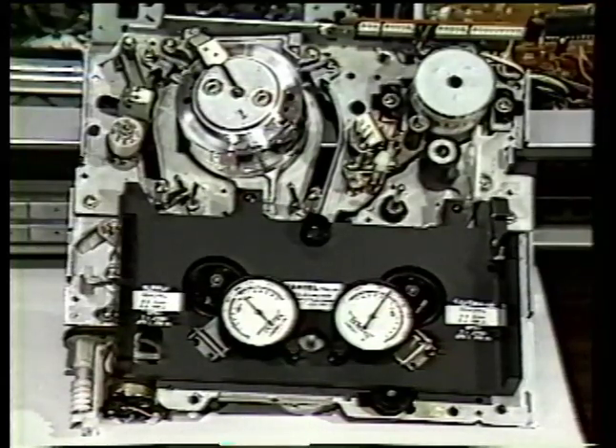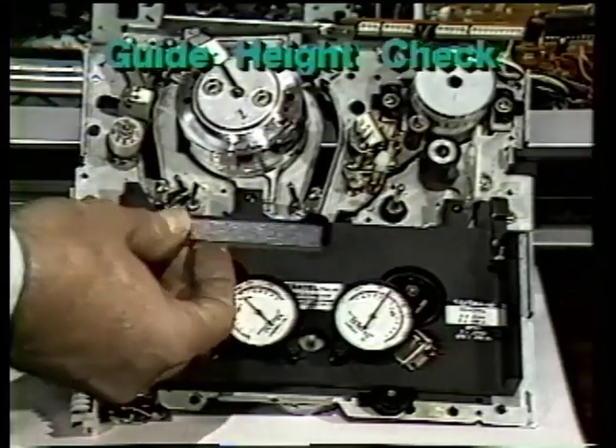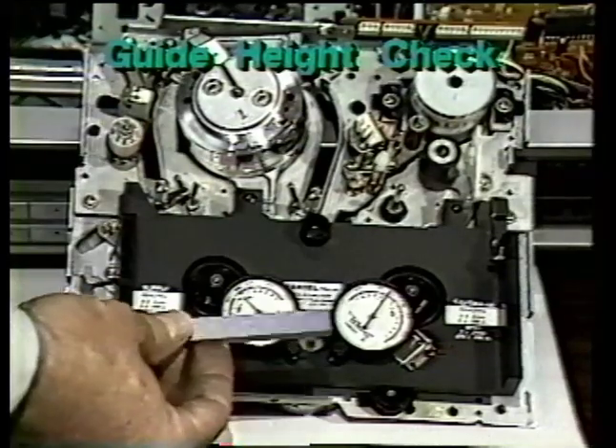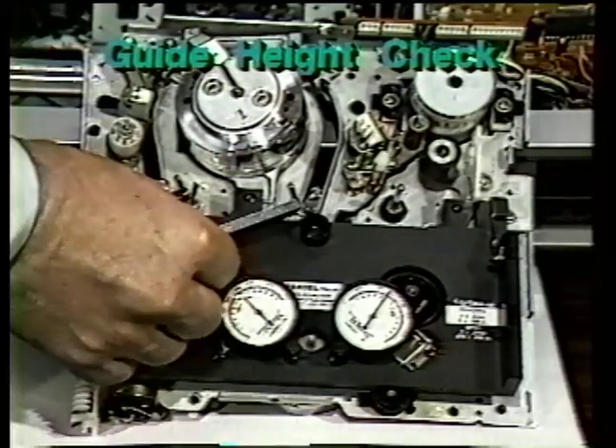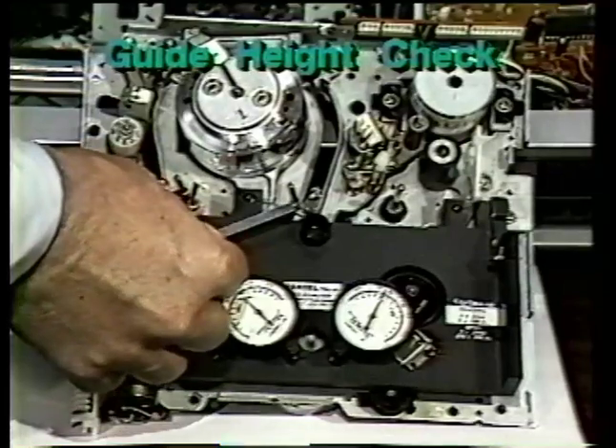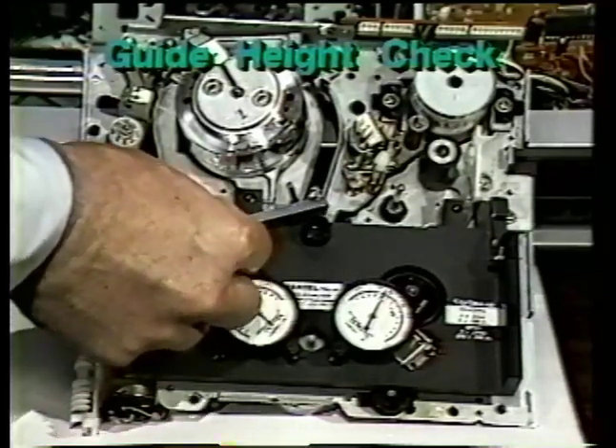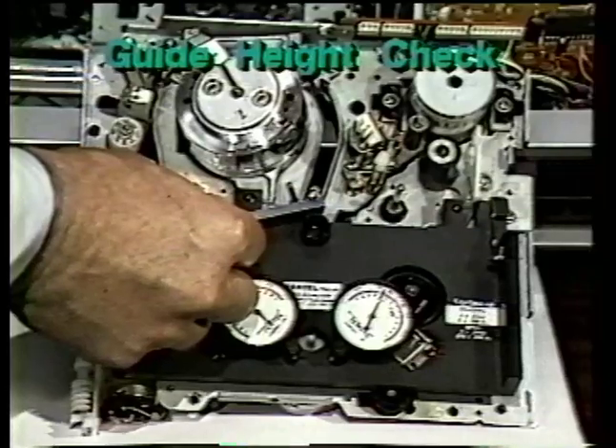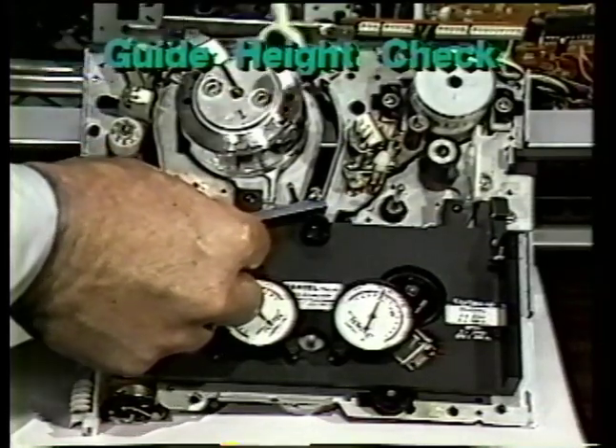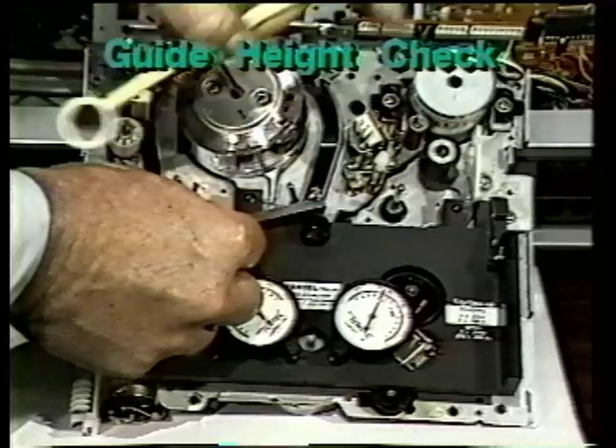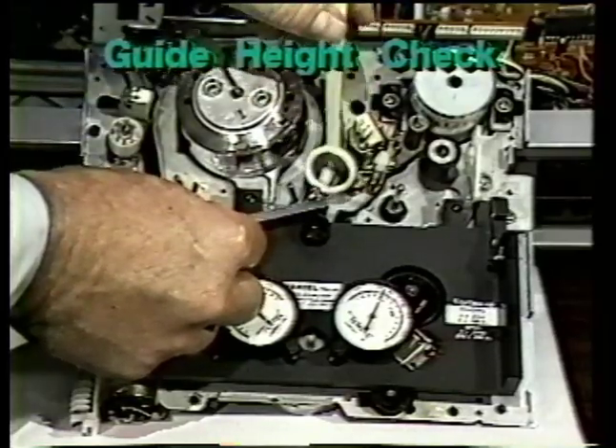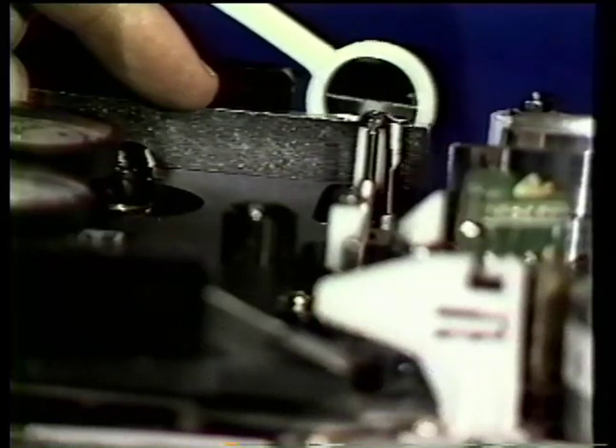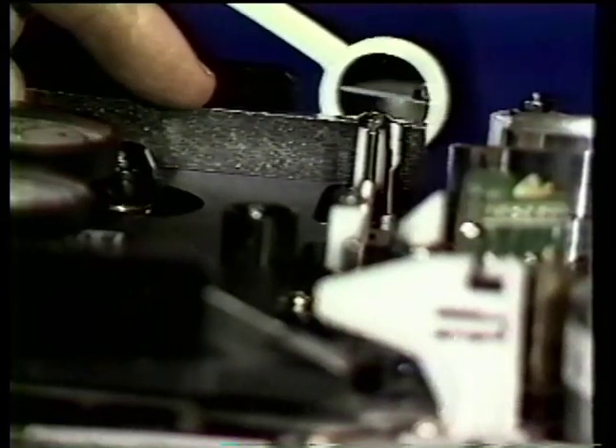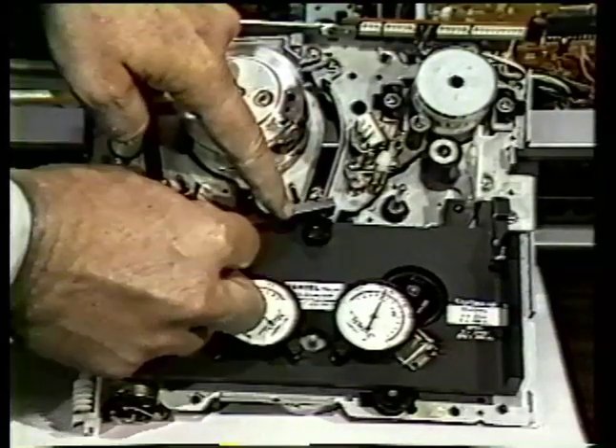Another test that we can do with the tush gauge is that it comes with a metal block. The metal block has been precisely controlled to a half an inch wide. As we slide that across the top of the plate, because the plate thickness has been controlled, we can actually detect if those guides are too high or too low, and as we'll show in a diagram, they're adjusted with a little screwdriver across the top. You can actually look in from the side with a mirror that's also provided to see if that guide height is set up properly.